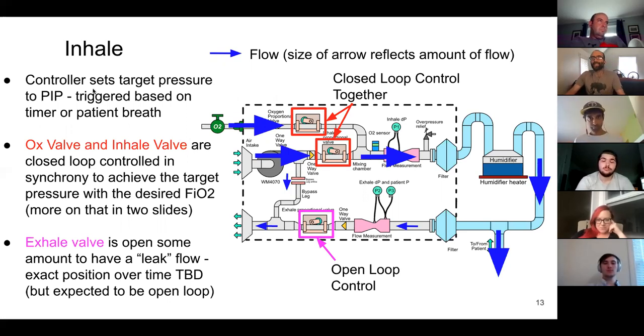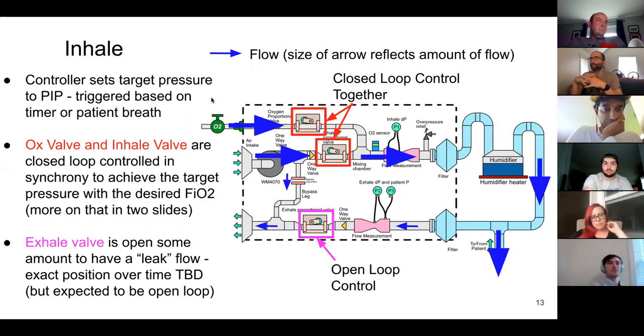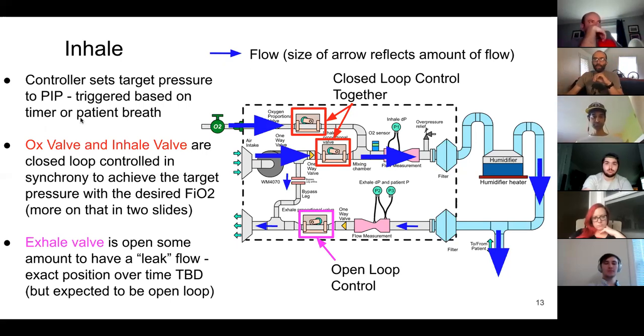So the first slide covers the inhale state. Just on states and modes for a second: modes refers to the different control modes, like SIMV or assist control—basically how the ventilator as a whole is functioning. States refers more to what's happening instantaneously—what's happening during inhale, what's happening during exhale. The bypass leg orifice probably shouldn't be shown as fixed; it's just saying we may add an additional restriction there, treating the leg as a resistance that's tunable to allow different pressure-flow relationships.